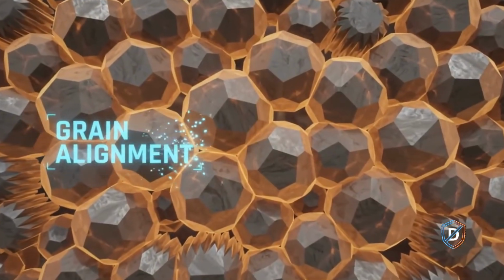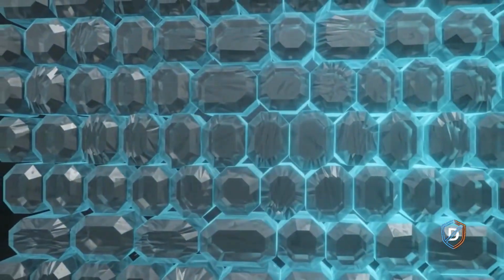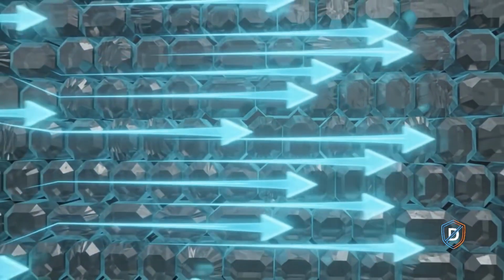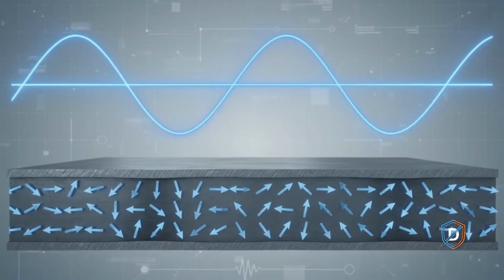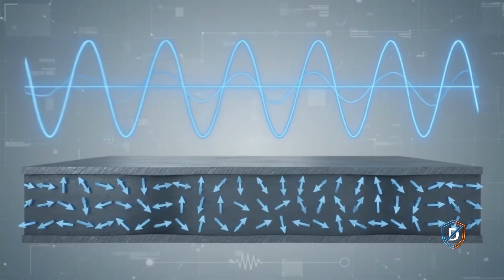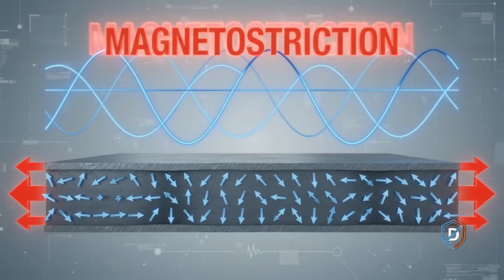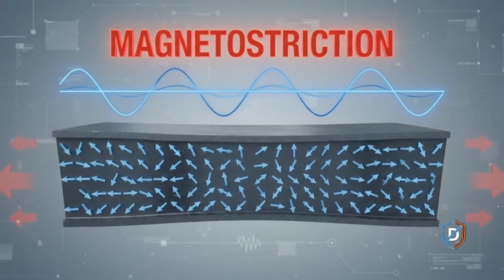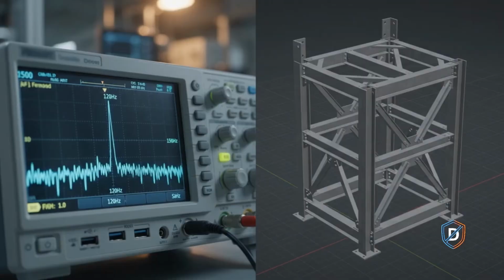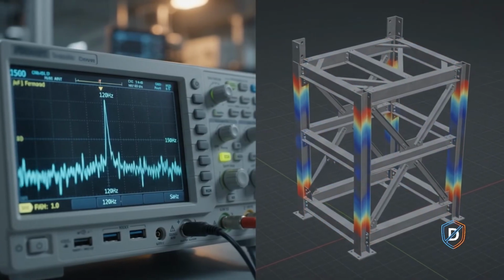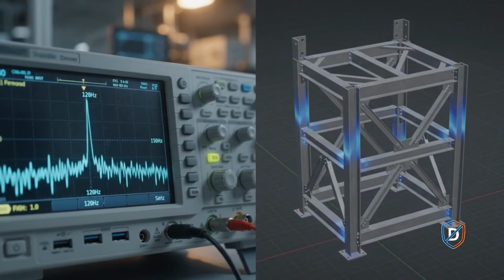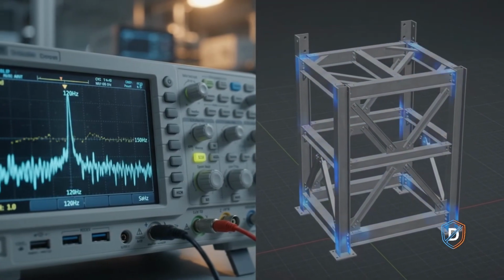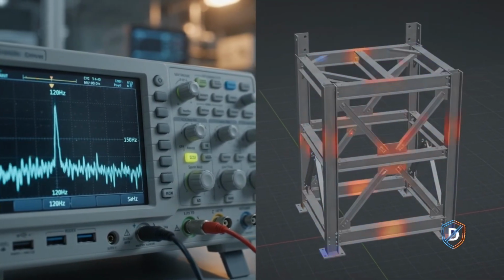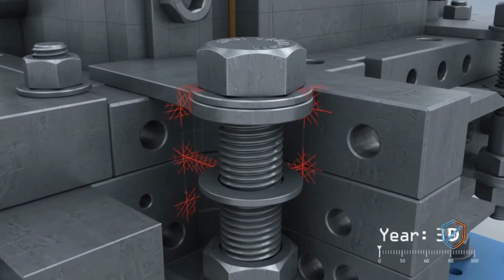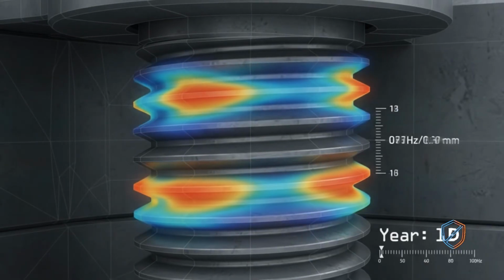Engineers stretch and roll this steel to align its atomic crystals in one precise direction, making magnetic travel effortless. As alternating current cycles, magnetic domains inside the steel realign, physically stretching the metal with every wave. Because the steel stretches on both positive and negative peaks, a 60 Hz grid produces a continuous 120 Hz physical vibration. Over 30 years of continuous hum, these microscopic expansions grind structural clamping bolts loose.